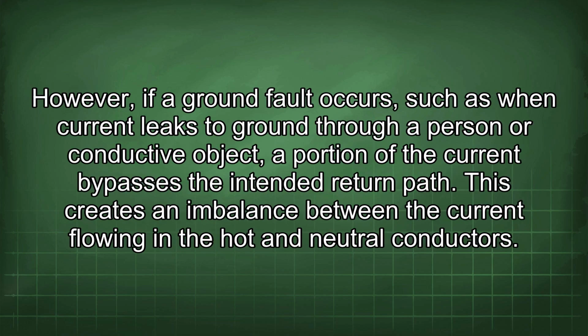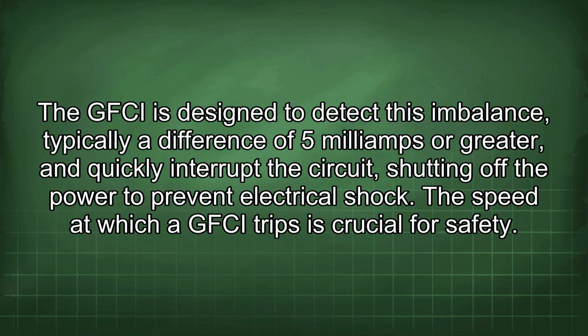However, if a ground fault occurs, such as when current leaks to ground through a person or conductive object, a portion of the current bypasses the intended return path. This creates an imbalance between the current flowing in the hot and neutral conductors. The GFCI is designed to detect this imbalance, typically a difference of 5 mA or greater, and quickly interrupt the circuit, shutting off the power to prevent electrical shock.